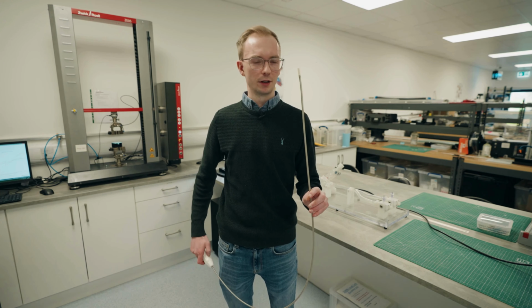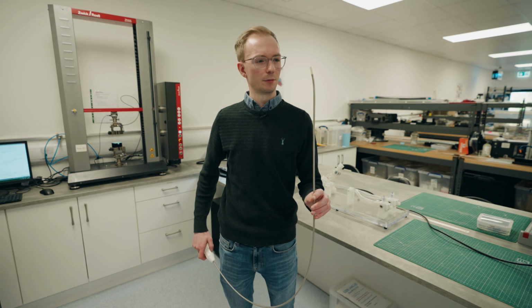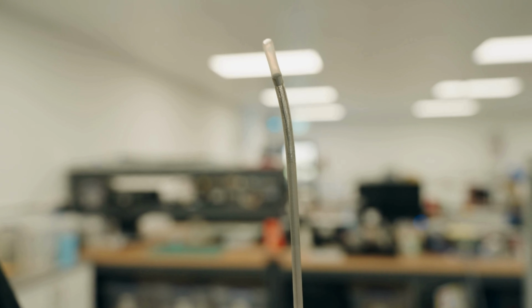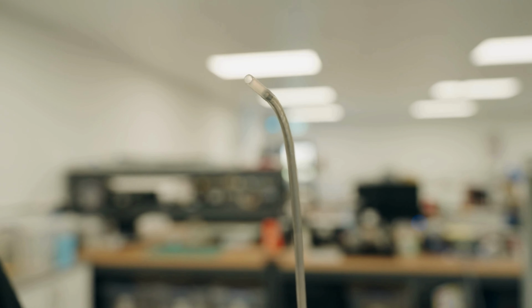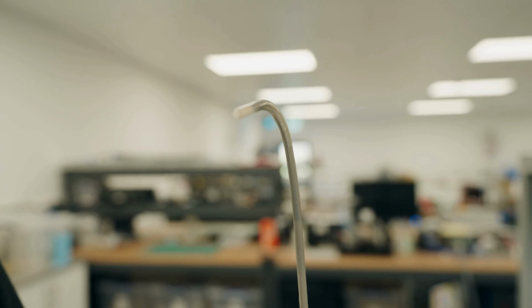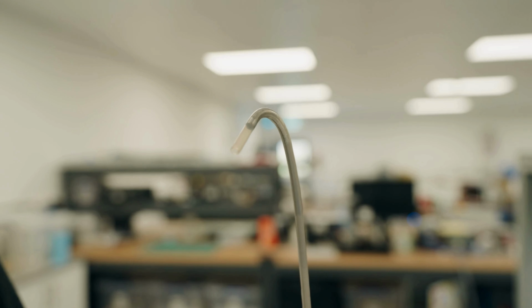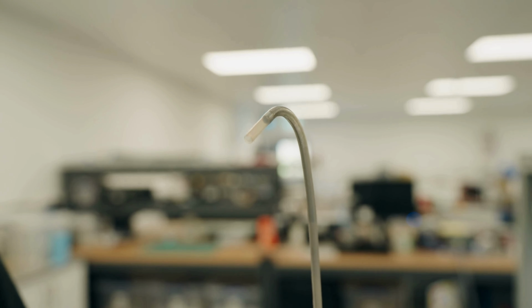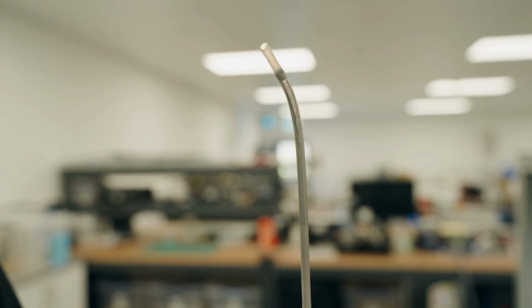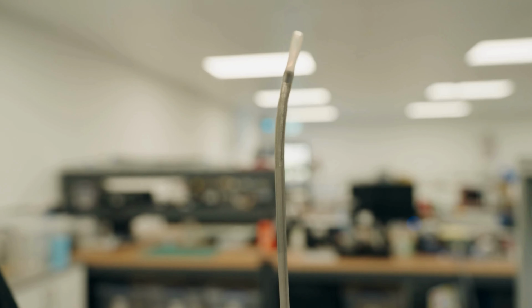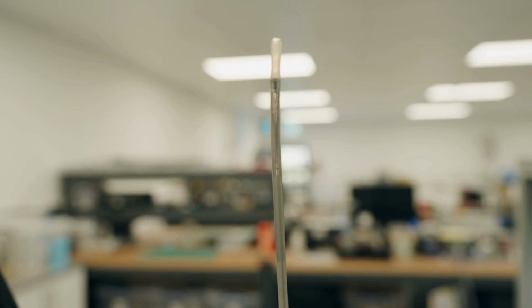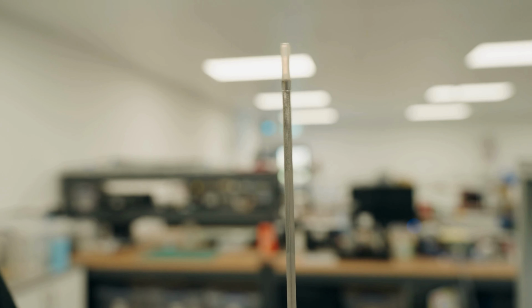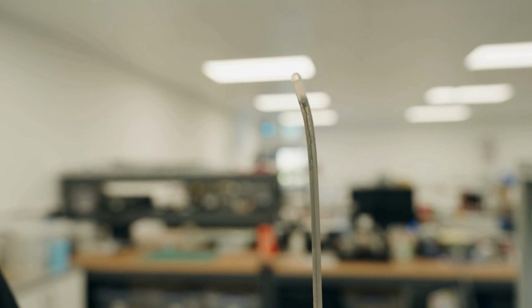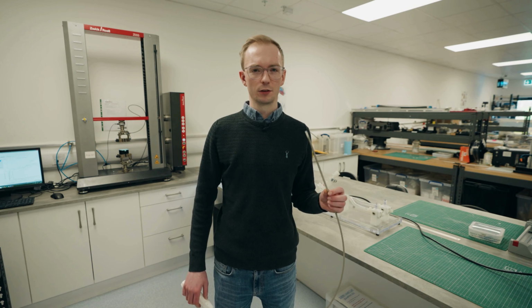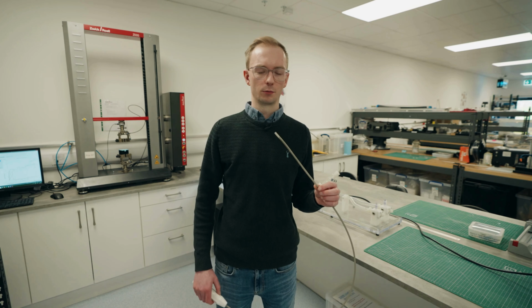This would be an example of a catheter that is used for, say, mitral valve repair or some other similar clinical applications. It uses varying durometers in the jackets to give it a good bending characteristic and profile. And what we do is we use a stiffer jacket in the proximal section and then gradually work up to a softer durometer jacket in the distal end to focus that bending force onto the distal end of the catheter. We also have some varying braid PPIs and other technologies in this catheter to give it that smooth and targeted bending. In this catheter here, we have a one direction pull ring, which is welded in place with the braid.